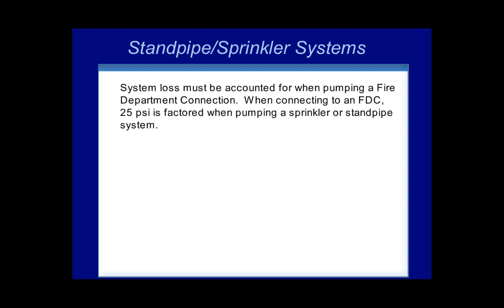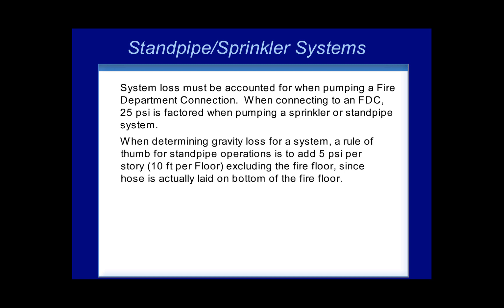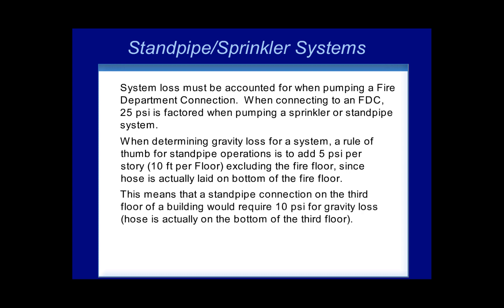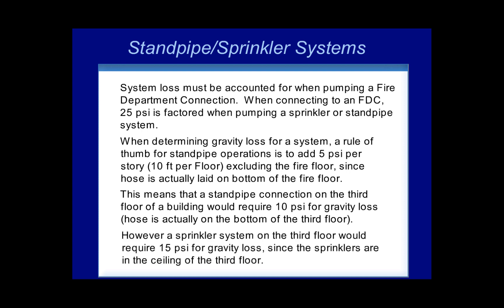Standpipe and sprinkler systems. System loss must be accounted for when pumping a fire department connection. When connecting to an FDC, 25 PSI is factored when pumping a sprinkler or standpipe system. A rule of thumb for standpipe operations is to add 5 PSI per story for 10 feet per floor, excluding the fire floor, since hose is actually laid on the bottom of the fire floor. A standpipe connection on the third floor would require 10 PSI for gravity loss. However, a sprinkler system on the third floor would require 15 PSI for gravity loss, since the sprinklers are on the ceiling of the third floor.